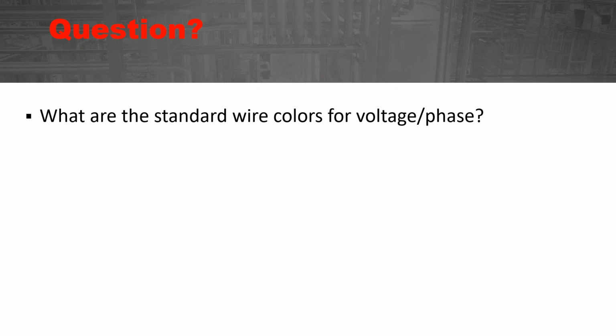I say, okay, then what about 277/480? What are the required colors for 277/480? And the general answer comes out: brown, orange, yellow, and gray. Well, certain colors are required in the National Electrical Code. Our grounded conductors or neutrals have to be white or gray, and we have some other options there. But the colors black, red, blue, and brown, orange, yellow are industry standard only. They are not requirements in the NEC.